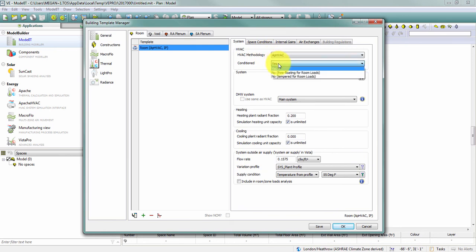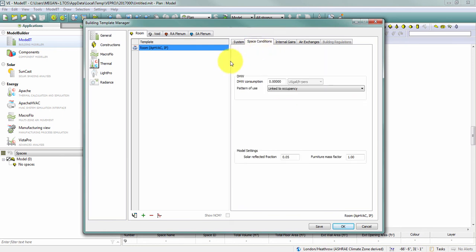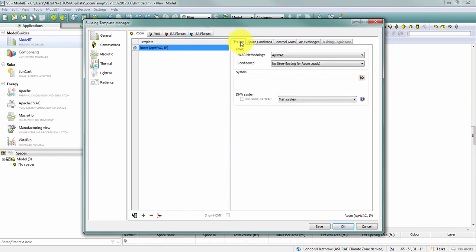If I change this to no, you'll see that those set points disappear and when my room loads are run, I will now allow this room to float. So any spaces on this template are going to float and the temperature will be a result of the gains and losses as if there is no mechanical conditioning of the space.